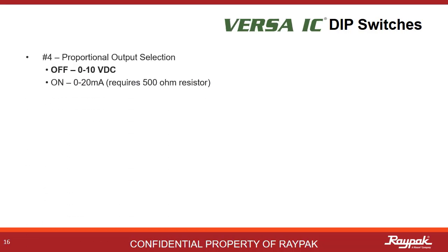Some three-way valves need a 0 to 20 milliamp signal instead of a 0 to 10 volt DC signal. If the valve selected needs a milliamp signal, then turn on Dipswitch number four. A 500 ohm resistor will be required.